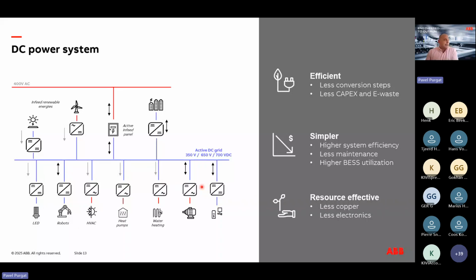Why? Because effectively we are decoupling ourselves from the AC side. Now, using the DC bus, common DC bus, of course, we get rid of many conversion steps, as you can see in the picture. We are more effectively using the raw materials, so we need less copper because of the voltage rating. And the system design on the grid edge becomes somewhat simpler. It is true that some components of the DC systems are a little bit more complicated, but the system design should be simpler.